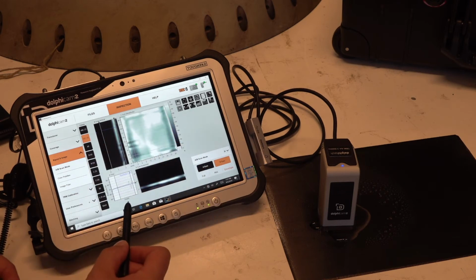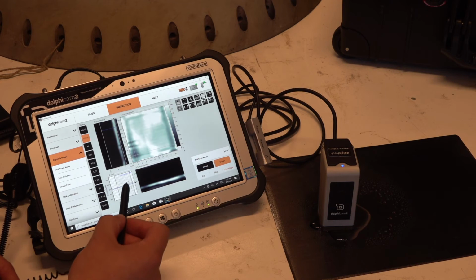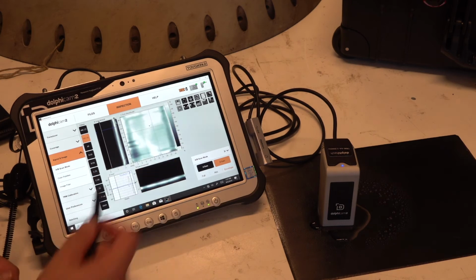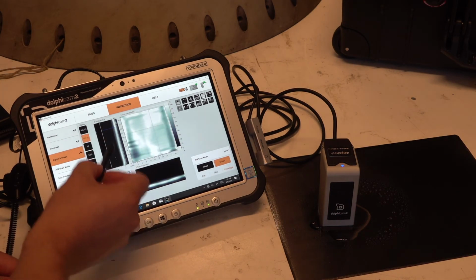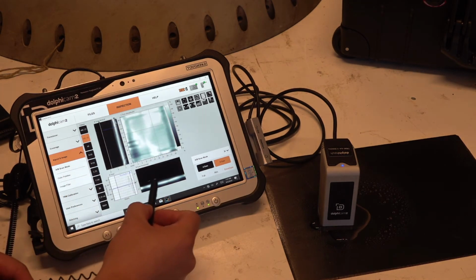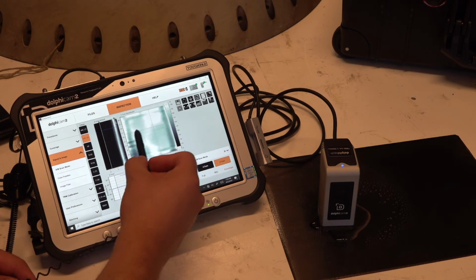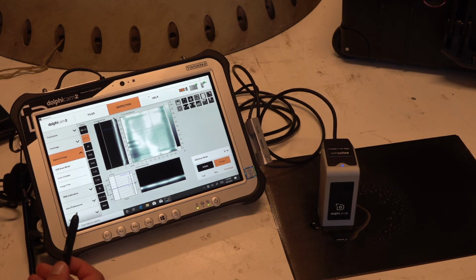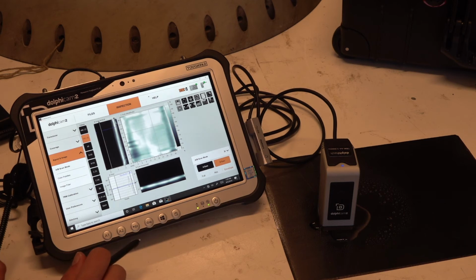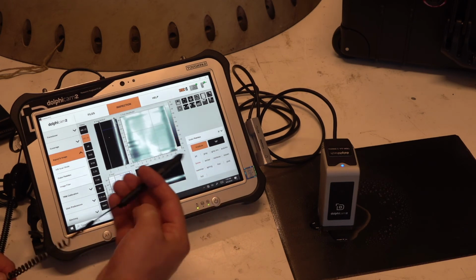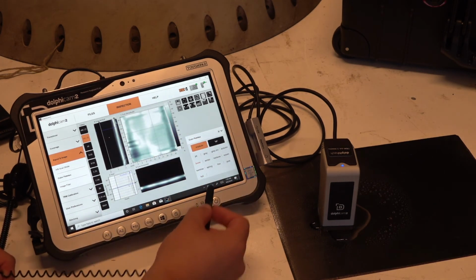Then we go to signal on image. As you can see we have 3 images here actually. We have an A-scan, that's one single point. So what's happening in one single point, I can select a point over here. Then we have the B-scan, that's a line of points, so that's a line where I'm measuring. And then we have the B-scan vertical, that's this line. And then we have the C-scan, and that's actually a 2-dimensional image of what I'm reading out of the DolphiCam, of the transducer.